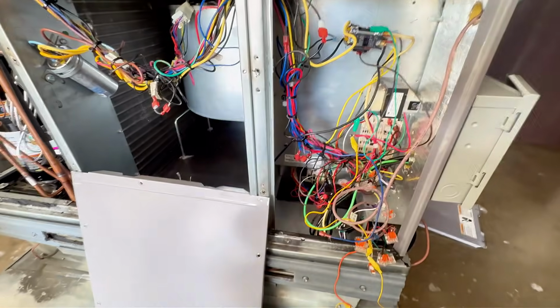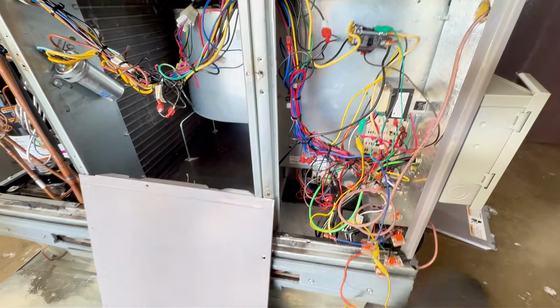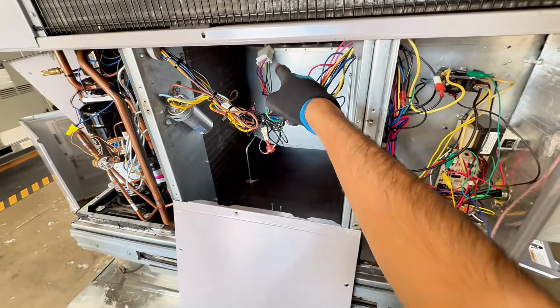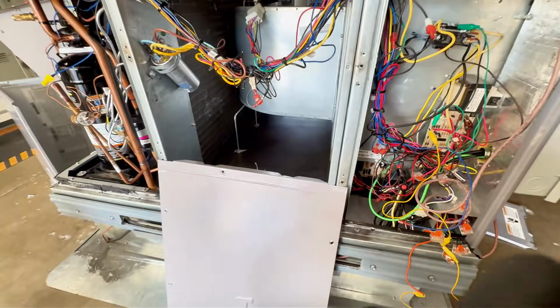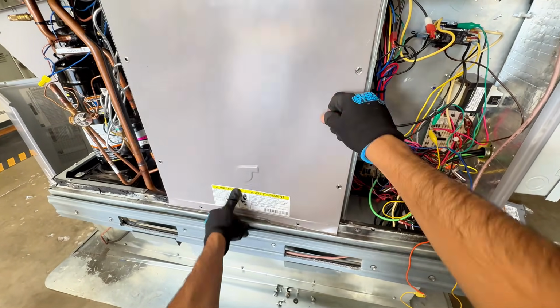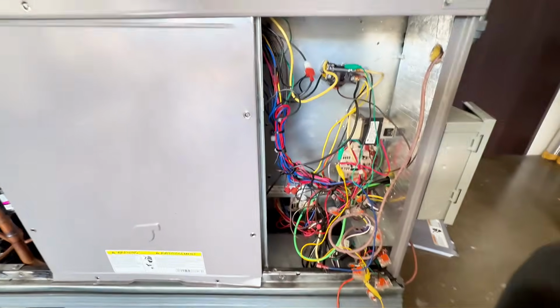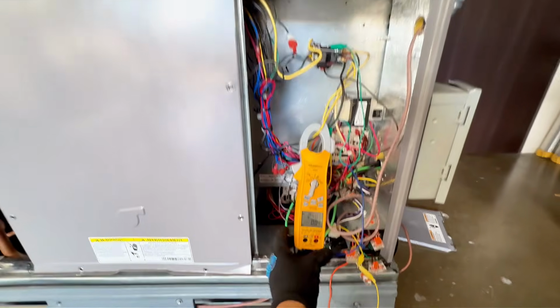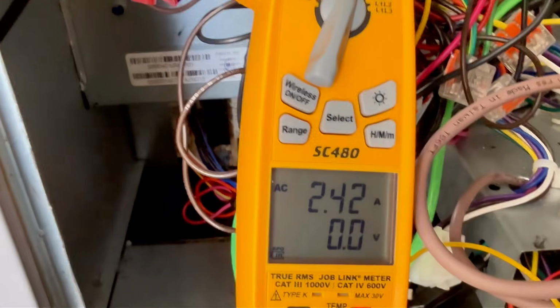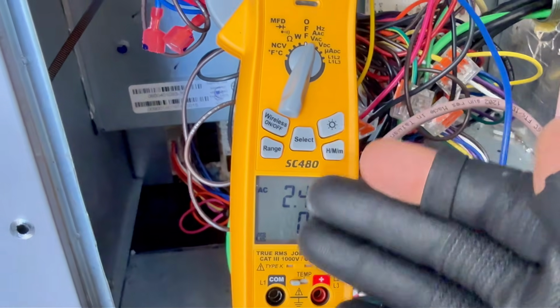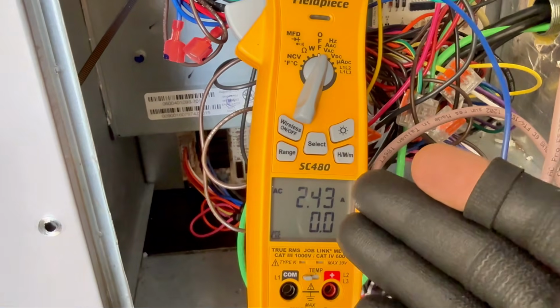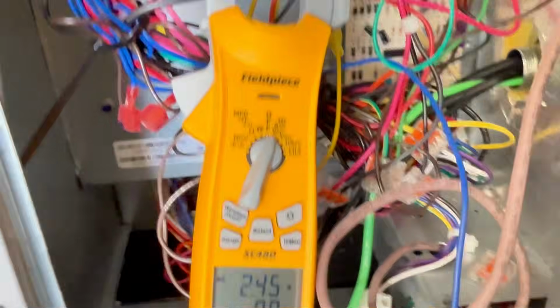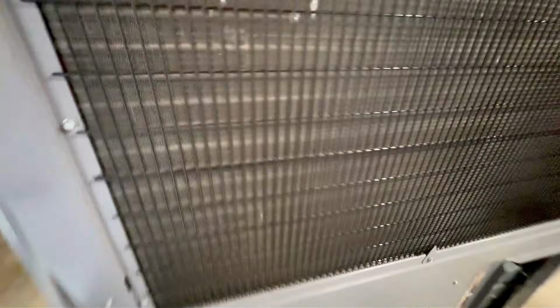With an ECM motor, are amps going to go down or up? So I'm going to go ahead and get the yellow wire. So have in mind, this one, I already determined which wire goes to the high voltage from there all the way over here. So actually, I do have to close this one off to get a proper amp reading. So I'm going to put it on amps, clamp it around the wire. And right now we are reading 2.4, and that's on the high speed, 2.4 amps. Okay, so I want you to remember that number, 2.4, because now we're going to create a restriction. And I'm going to create it on the supply side. So just give me 1 second. Okay.